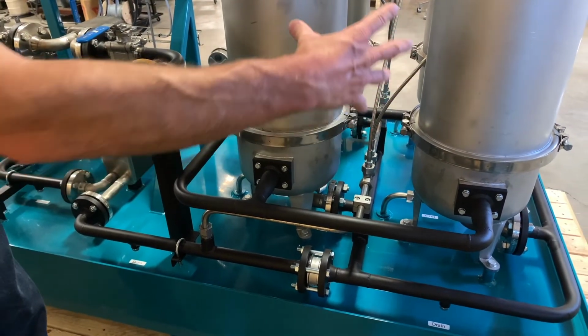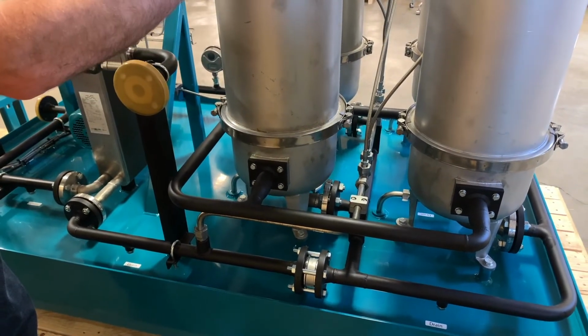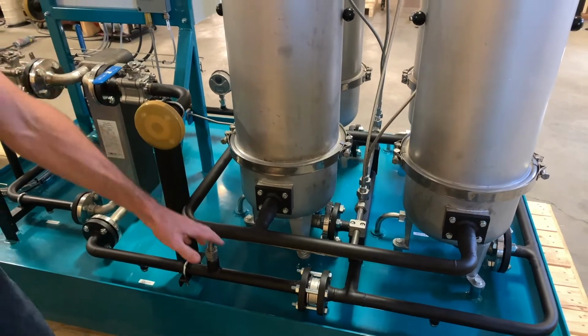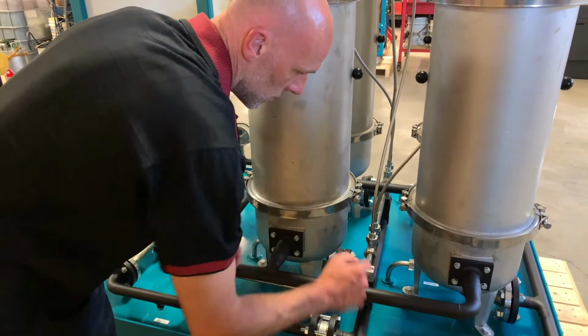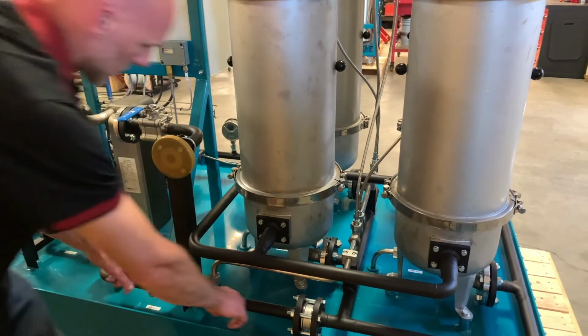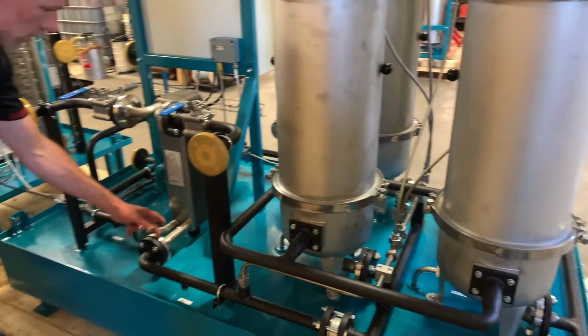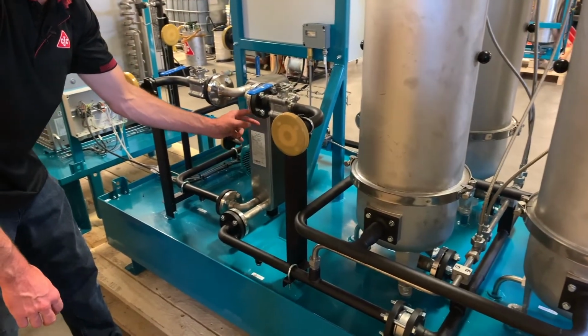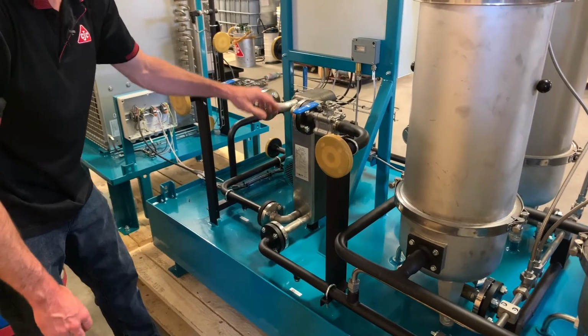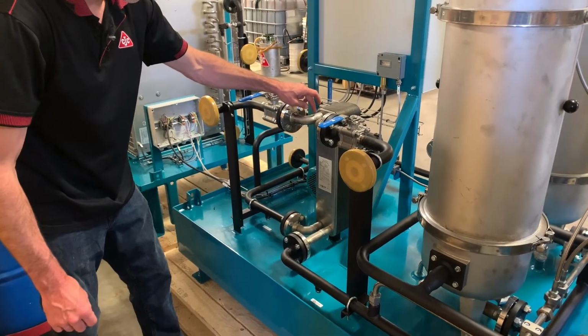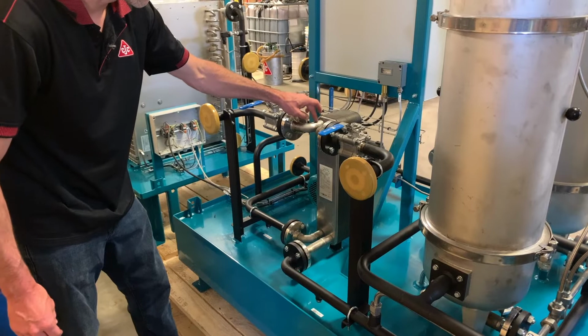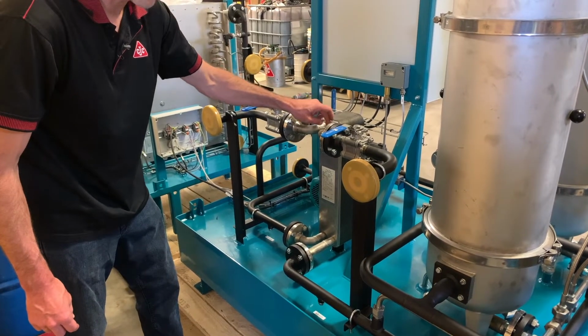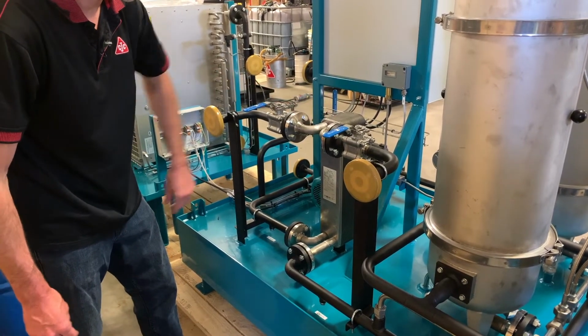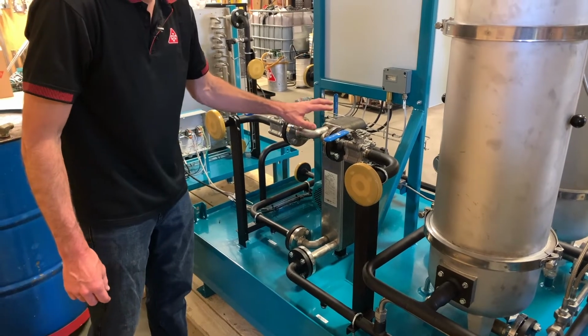The oil is pushed from the outside in through the filter media and down through the center, and the outlet manifold is down below here. So it comes this way, travels through the opposite side of the heat exchanger, and then to the outlet. So in this way, the heat exchanger helps to use the incoming hot oil to reheat the outgoing cold oil before it goes back into the system. So it's a very efficient way of managing the heat.